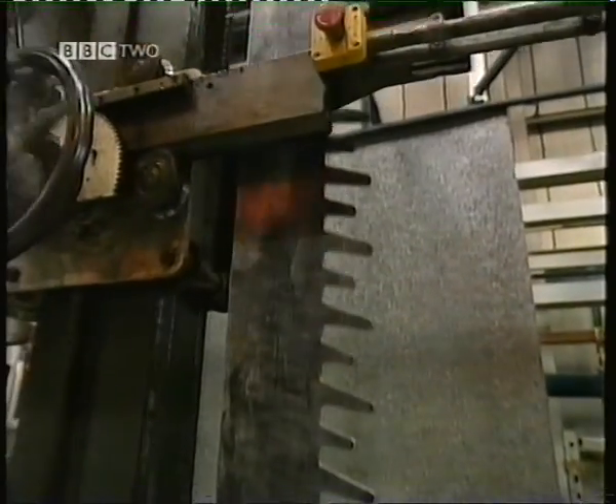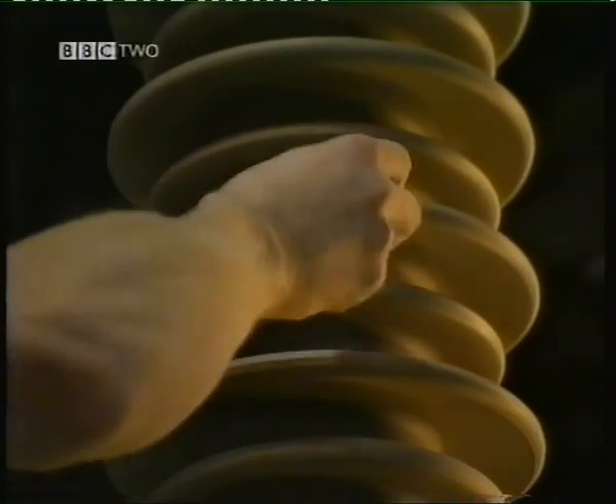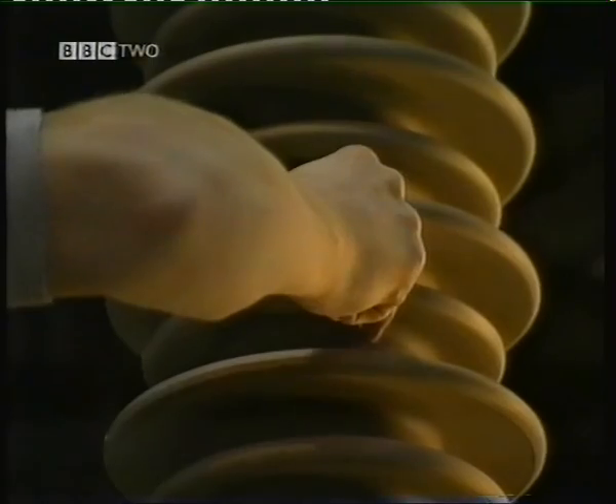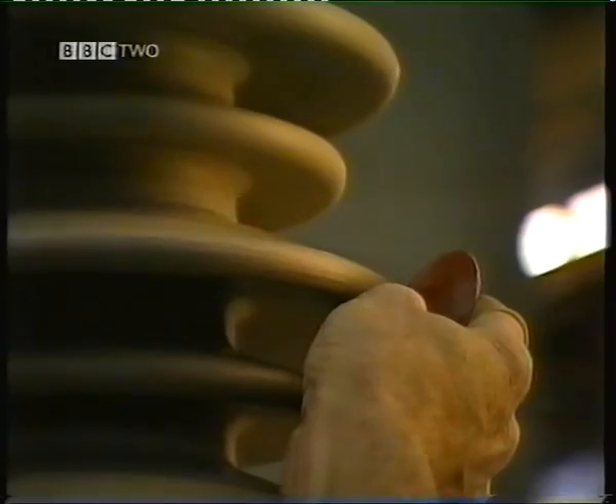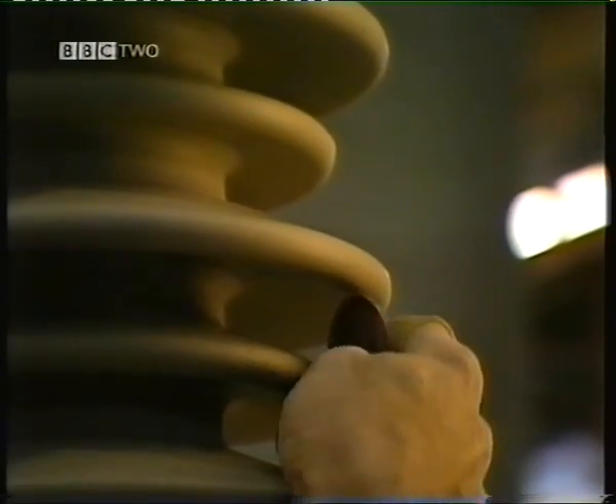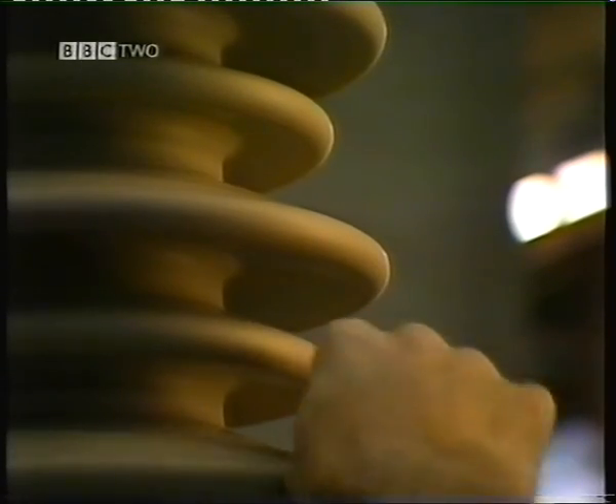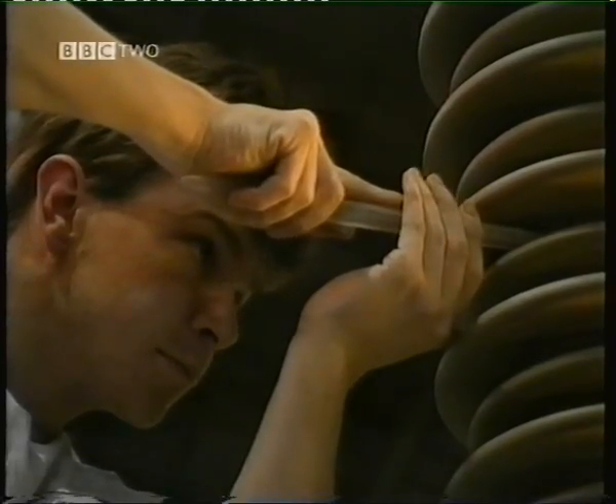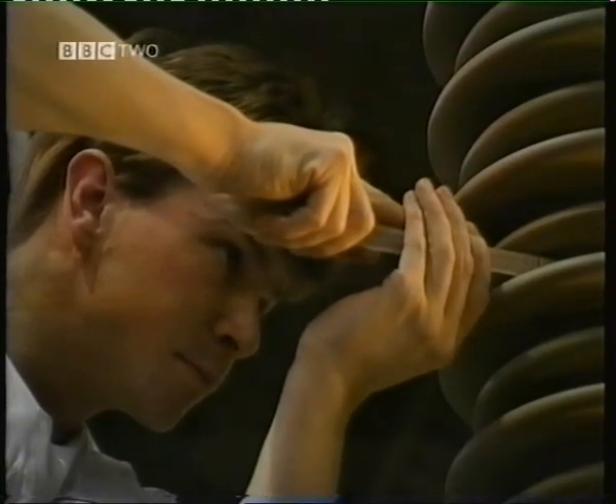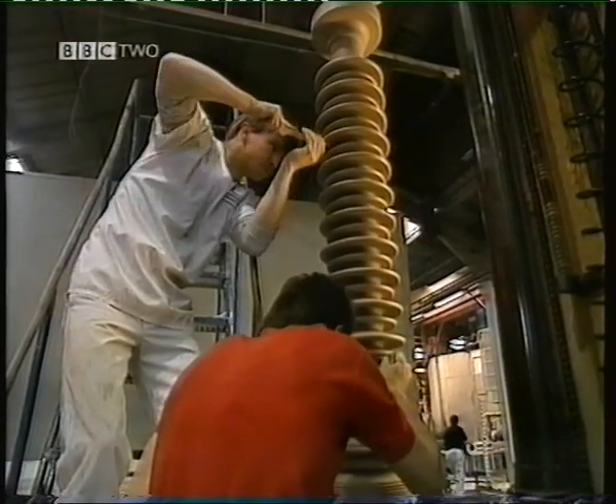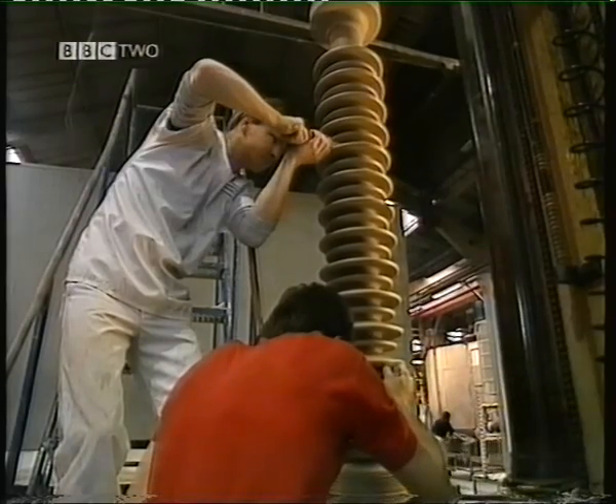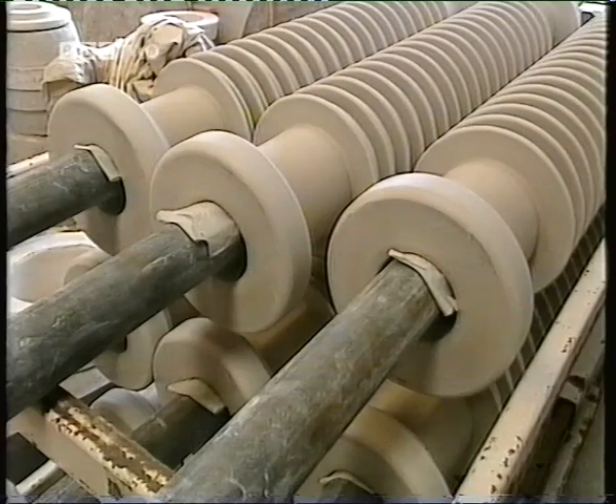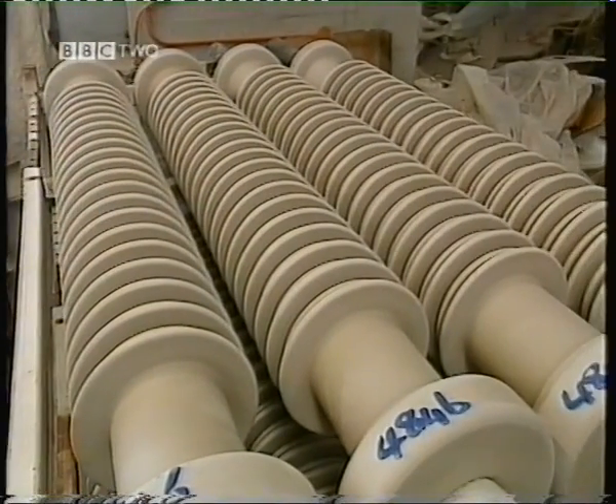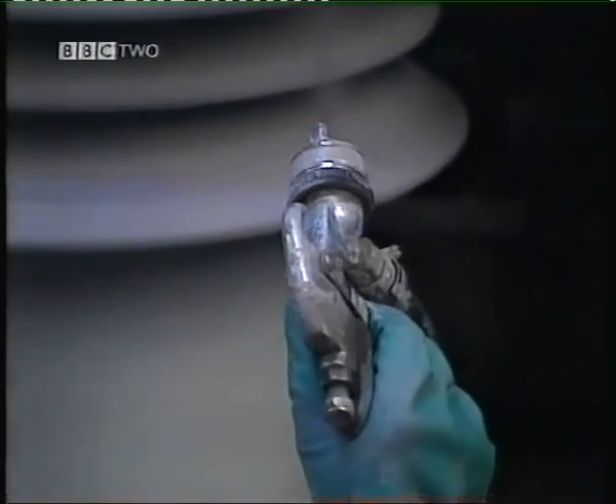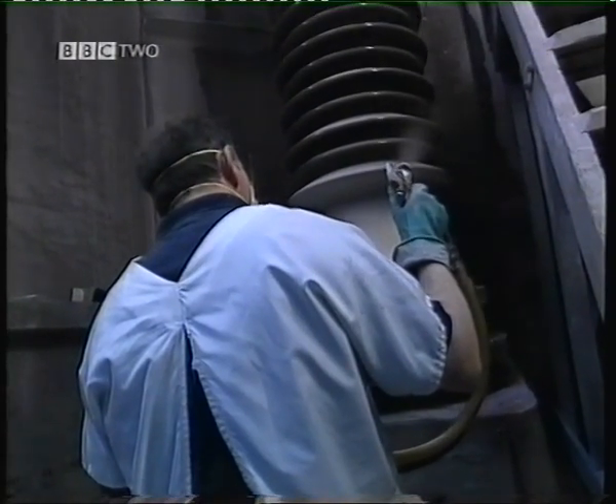The exact shape is produced by following a pattern on the machine and then hand finishing to remove blemishes. Any sharp bits would produce sites where electric stress concentrations could arise, lowering the breakdown strength of the system. Another period of drying is followed by glazing. The glaze further enhances the smooth surface finish and, as we'll see in a moment, has another purpose.